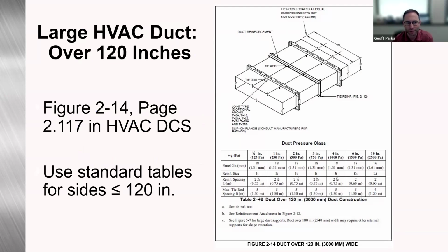Figure 2-14 has table 2-49, which covers duct construction options, requirements for ductwork over 120 inches on any side. Anything less than 120, you would use the standard duct construction tables.